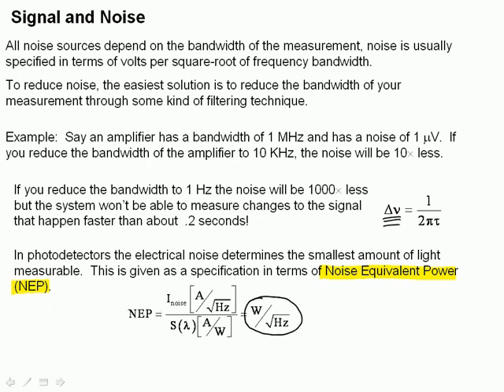What does this mean? If a photodiode were to have an NEP of, say, 10 to the minus 15 watts per square root of hertz, it means that if I have a measurement system with a 1 hertz bandwidth, a very narrow filter, the signal-to-noise ratio I measure from that photodiode in an ideal case is going to be equivalent to the signal that 10 to the minus 15 watts would give me. That's where my signal-to-noise ratio is equal to 1, and that means the smallest signal I'll be able to detect is 10 to the minus 15 watts.